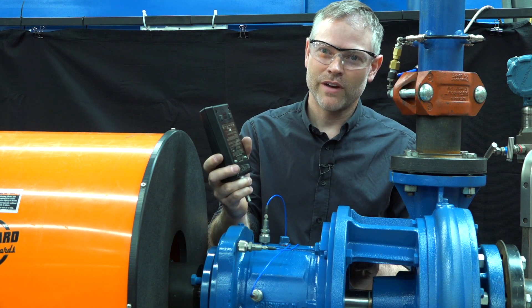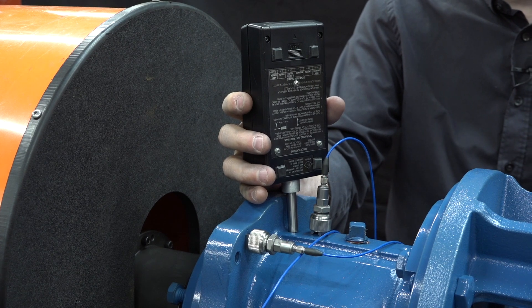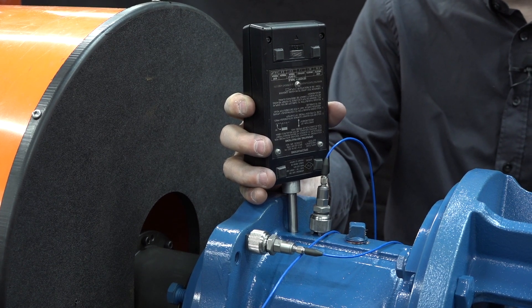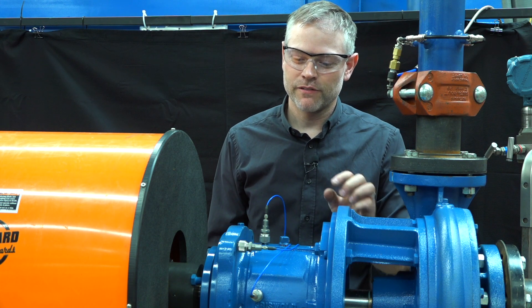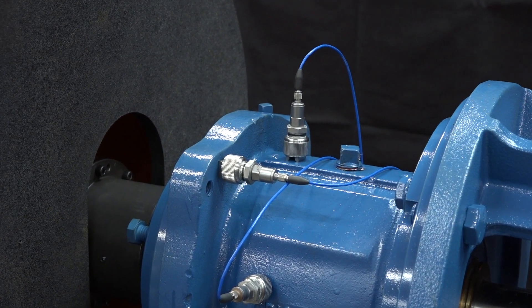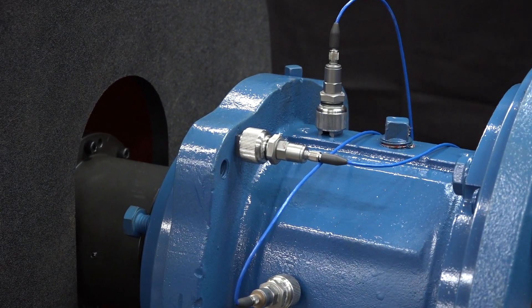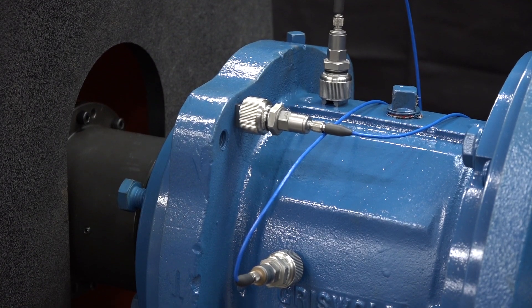Instruments such as handheld vibration meters can be used where you hold the instrument up against the pump to get a vibration reading. More advanced equipment can be used to monitor vibration, such as sensors that are attached to the pump. This can allow us to collect data continuously about the vibration levels, and we can measure tri-axial vibration as well.